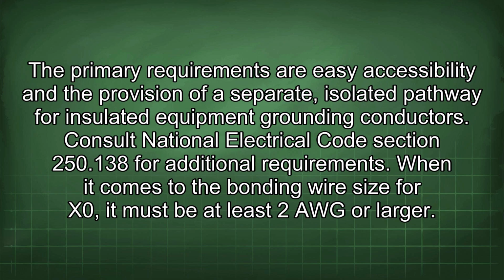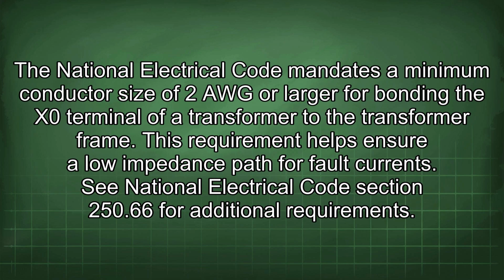When it comes to the bonding wire size for X0, it must be at least 2 AWG or larger. The National Electrical Code mandates a minimum conductor size of 2 AWG or larger for bonding the X0 terminal of a transformer to the transformer frame. This requirement helps ensure a low impedance path for fault currents. See National Electrical Code Section 250.66 for additional requirements.